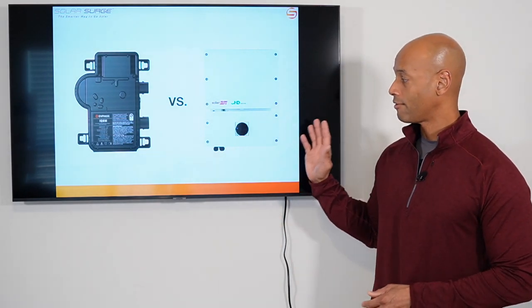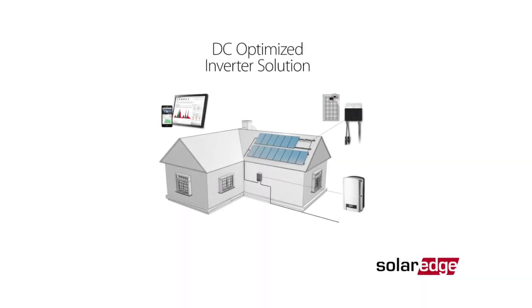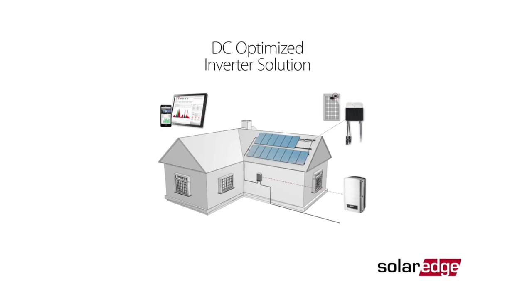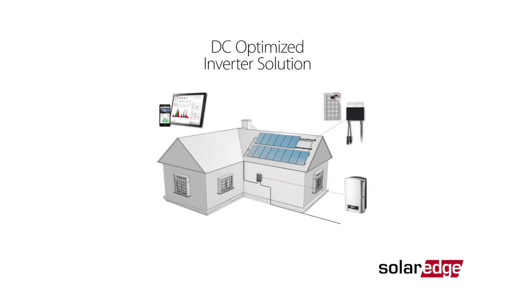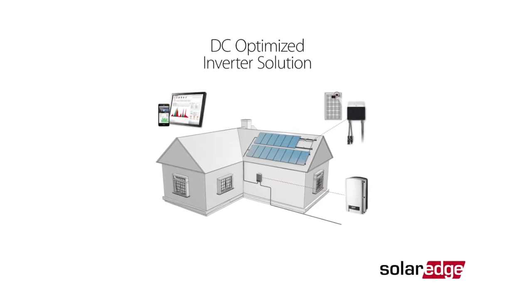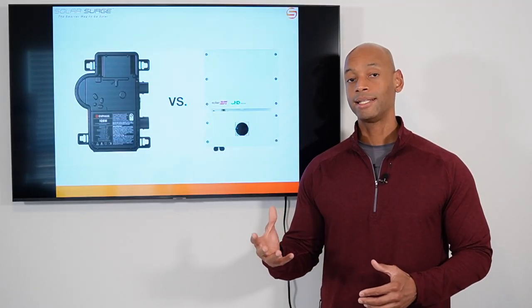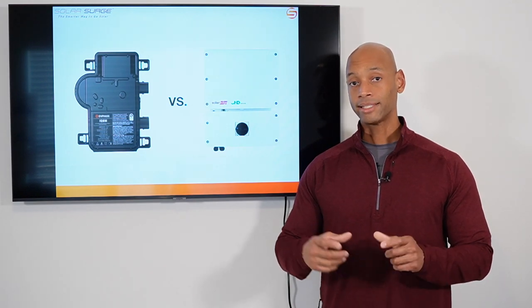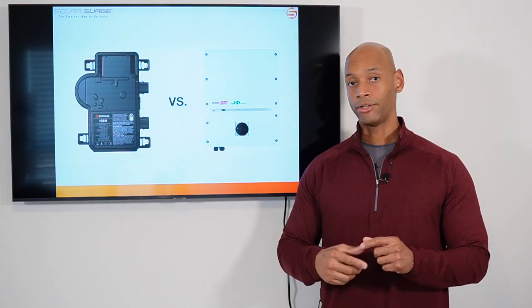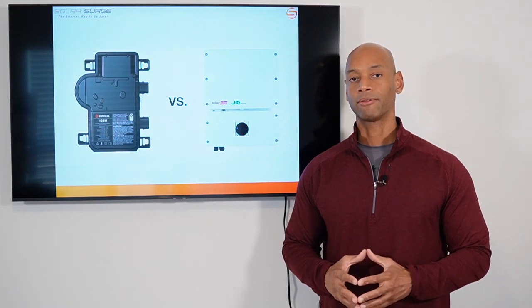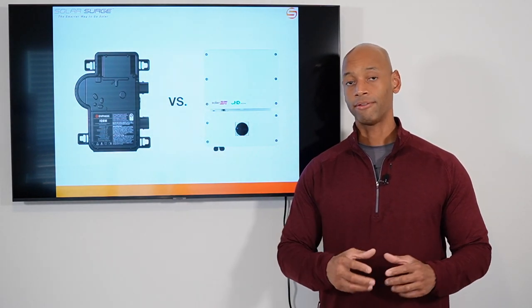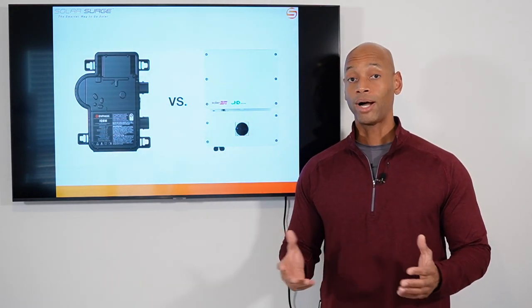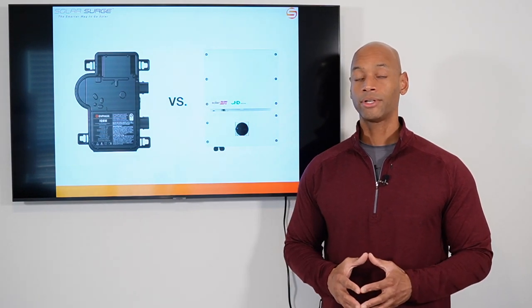Now about four years later, SolarEdge came on the scene with the DC optimizer solution. What the DC optimizer solution did was it basically put a DC optimizer device on each individual solar panel. So basically each panel had a unique serial number and you could track performance coming from each optimizer unit and thereby by each panel. But the wiring was as simple as the old string inverters.